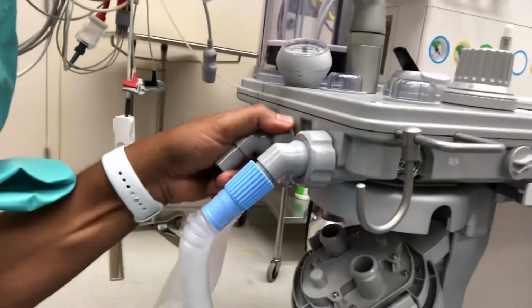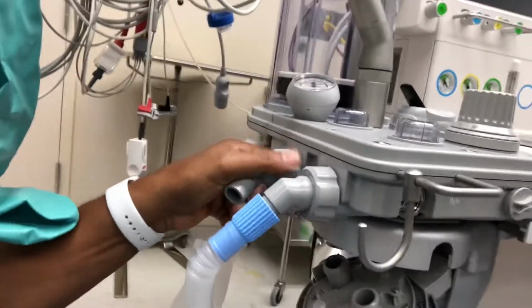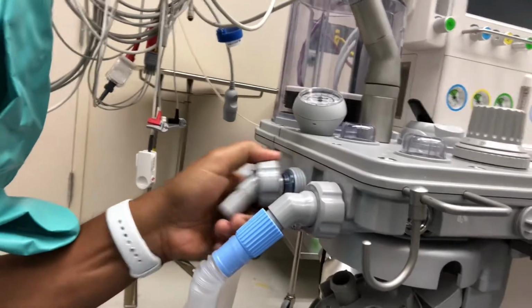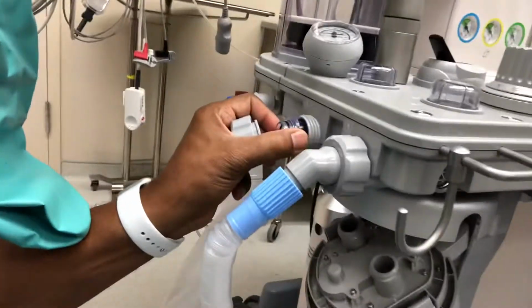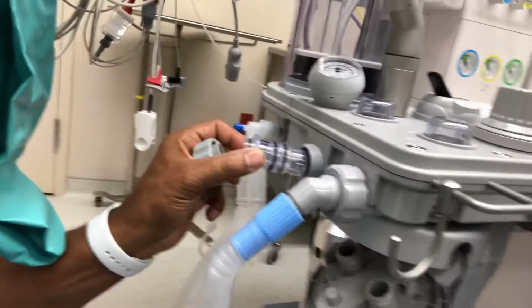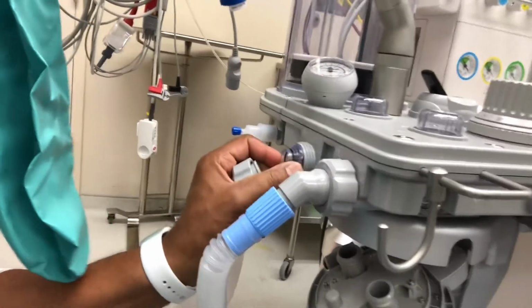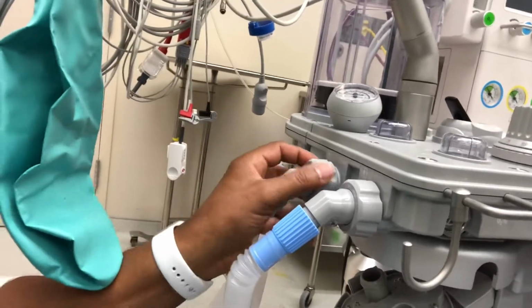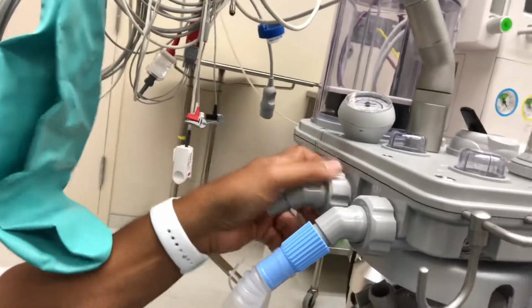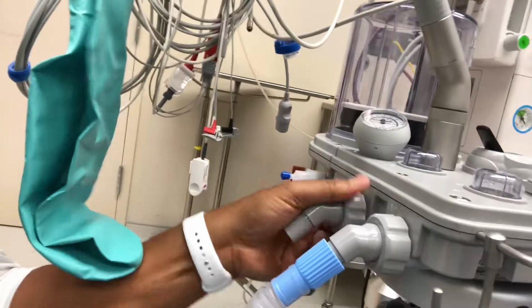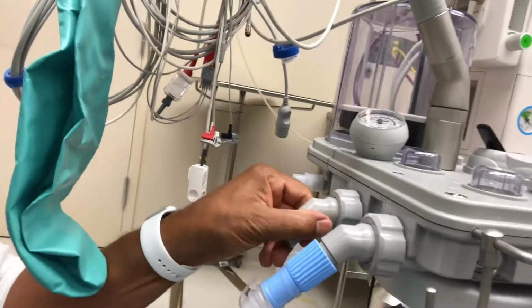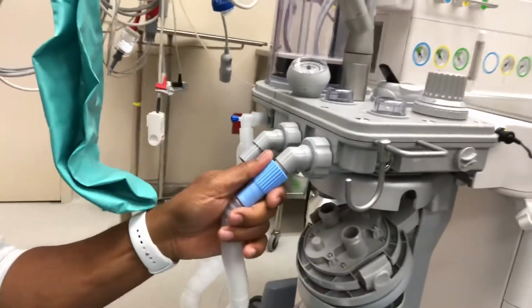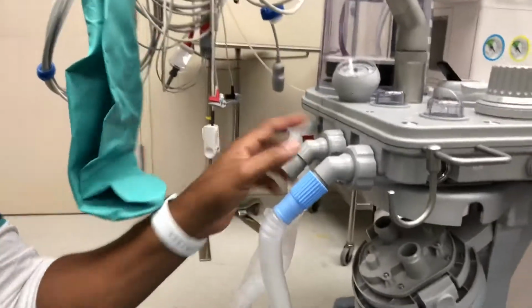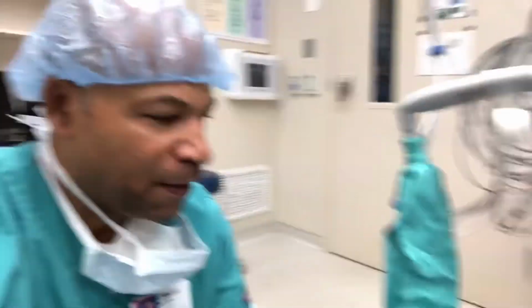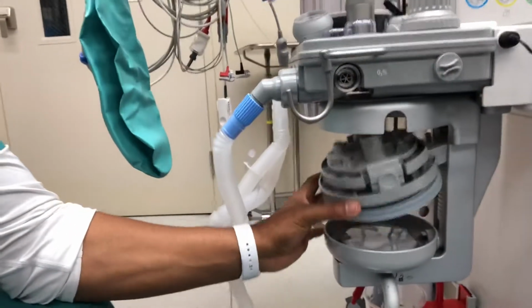Another area here that I want to show you is the flow transducers. These are also prone to sometimes cause problems, and you can tell if you're having problems when you look at your display and see that your volumes are off. These might be a good area to start looking and cleaning these out or calibrating. That's part of the procedure for the calibration of the flow sensors. And there's two of them on each side. Basically just unscrew this, and you put them back in place like I did.